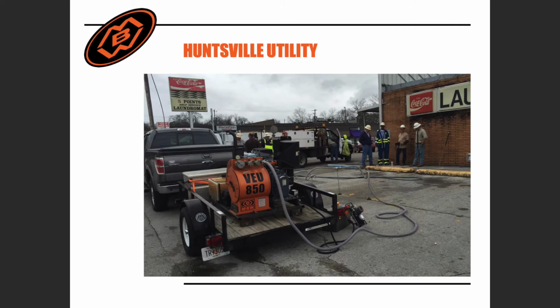We started running the VEU and could see the LEL levels being pulled away from the building. On this job, we ended up pinpointing the leak on the second yellow dot in the middle of the picture here. That day, the utility ended up purchasing a VEU because it responded so well at a high-level emergency.